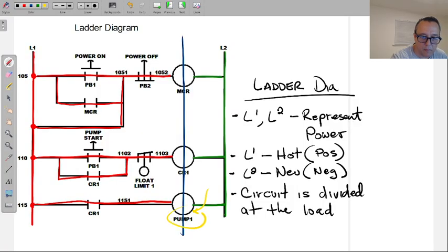We have some labels, we got a pump. If that pump is not on, yes, I want to make sure there is power. So I'm going to check power between L1 and L2, between the hot and the neutral, or the positive and the negative.